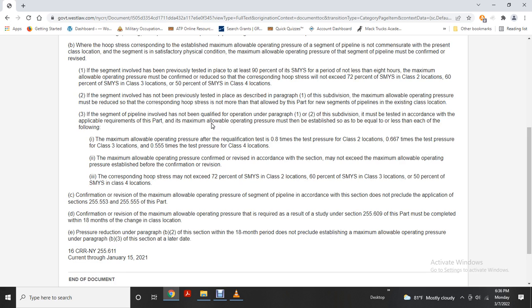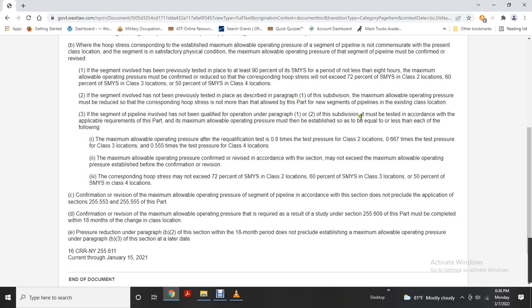New segments of the pipelines in existing class location. If the segment of the pipe involved has not been qualified under paragraph 1 and 2 subdivision, it must be tested in accordance with the applicable requirements of the part. Maximum operating pressure must be established as equal to or less than each of the following. Maximum operating pressure qualification testing: 0.8 times the pressure for Class 2, 0.667 times the pressure for Class 3, 0.555 times the pressure for Class 4. Maximum allowable operating pressure considered revised in accordance with the section may not exceed the maximum operating pressure established before the confirmation or revision.